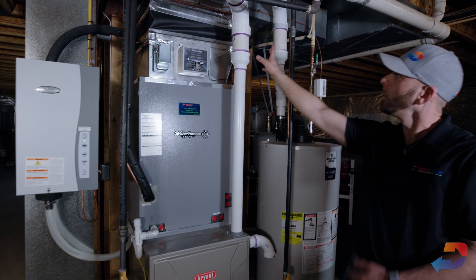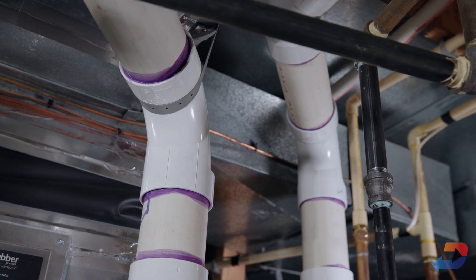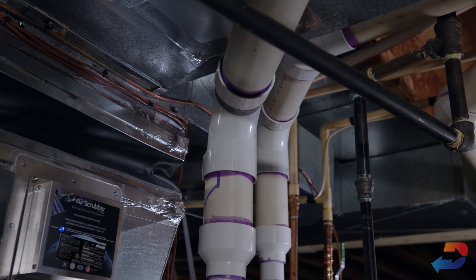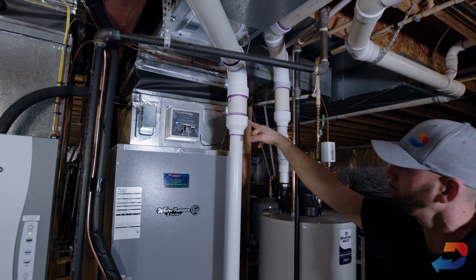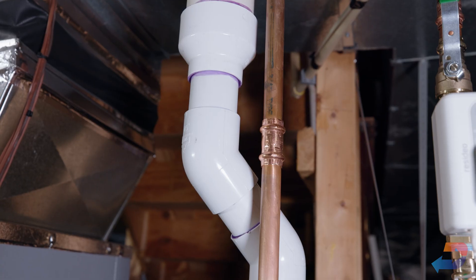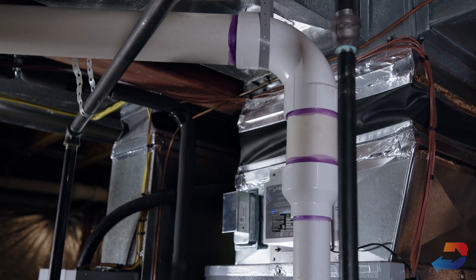The last thing I wanted to hit on was this reduction. In the first video, it was in the horizontal position — as the pipe fills, it blocks a portion of the pipe. We've now relocated it to the vertical portion, which meets manufacturer's spec. And the same with this one on the water heater — that one was on a 45-degree angle, and we now have it in the 90-degree vertical position.